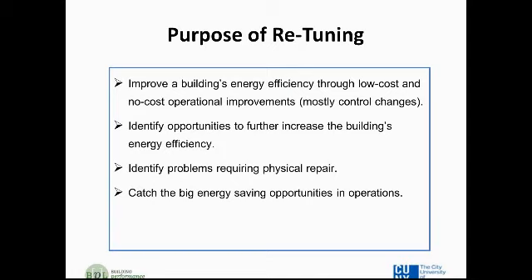There are 9 building retuning measures that were developed by the Pacific Northwest National Laboratory, or PNNL. We run through all of those in the class. We would also identify problems that may require physical repair. Typically, those are very low-cost repairs having to do with sensor calibration, or simple things you may notice while going through the building retuning process and your walk down, like broken linkages in your dampers, which can in fact lead to vast energy losses.